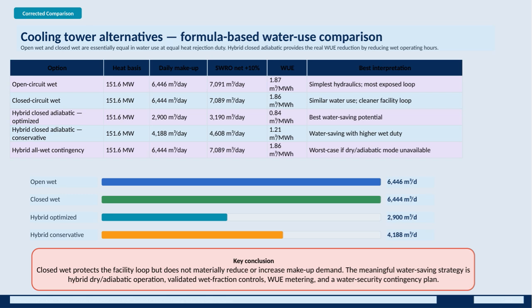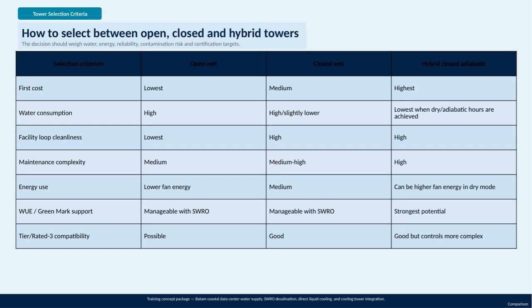When selecting between open, closed, and hybrid cooling towers, several important factors need to be considered. These include water usage, energy consumption, system reliability, risk of contamination, and whether the solution meets specific certification targets. Looking at the key criteria, open wet towers generally have the lowest initial cost, but come with higher water consumption and lower facility loop cleanliness. They also have moderate maintenance complexity and lower fan energy use.